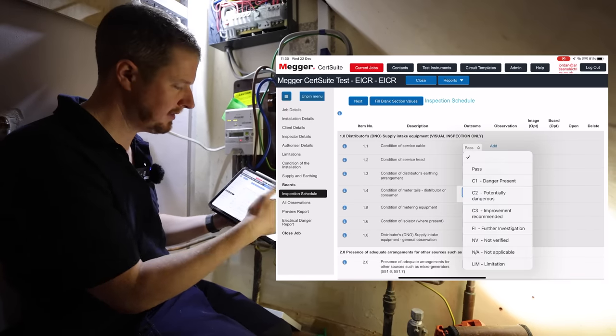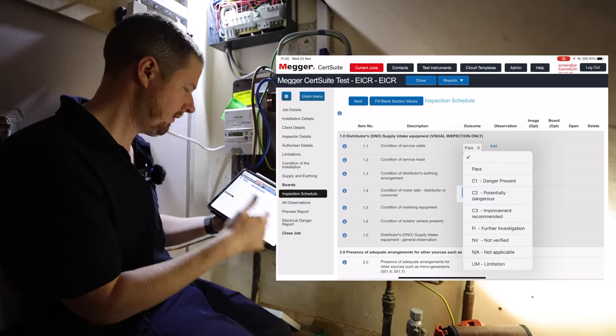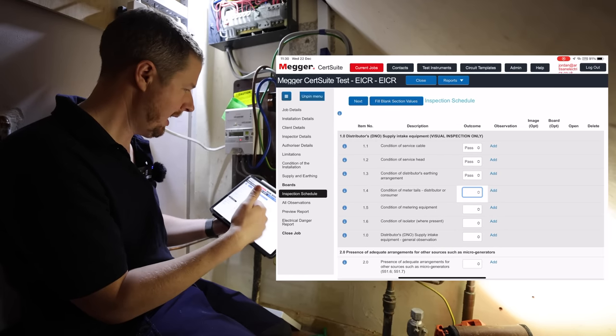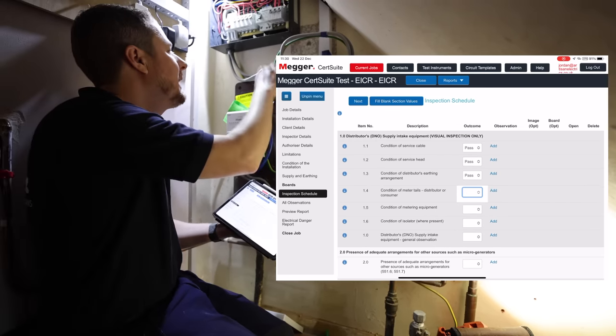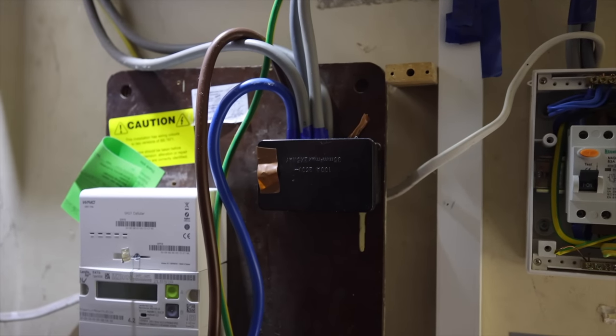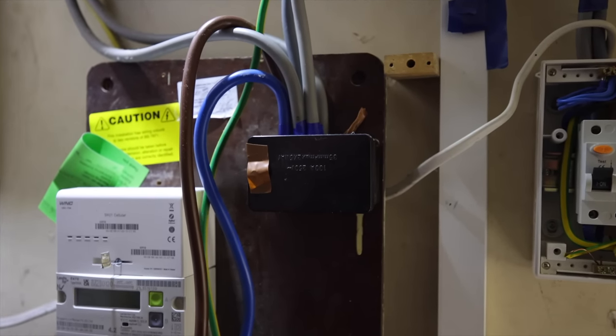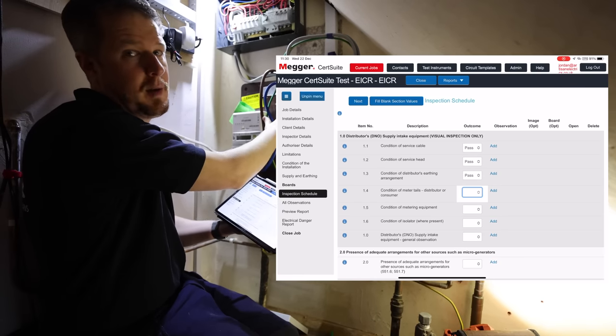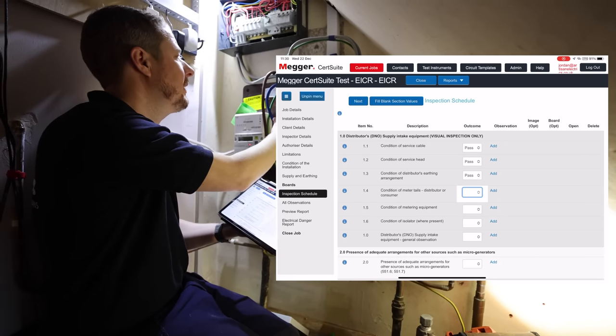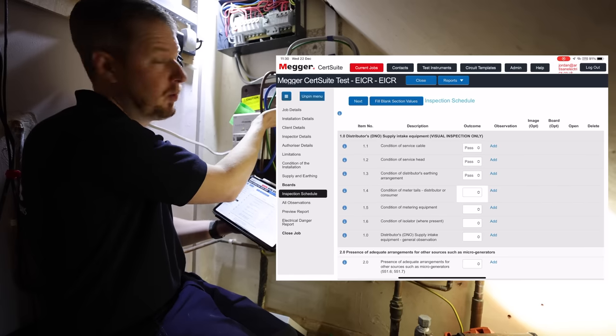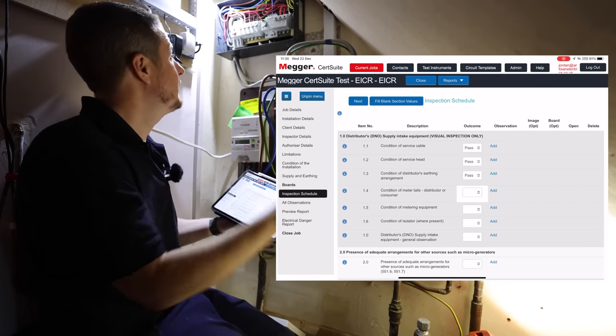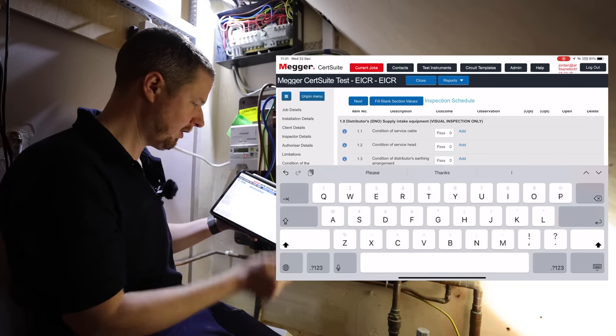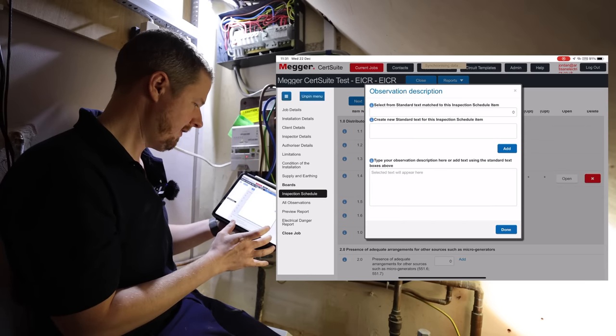So I'm just going to go through this. This is a bit boring, I'm not going to show you all of this, but it's just a tick box exercise going through. And if we find any issues, like the Henley block, for example, that is a codeable offense having it upside down, because the top surface does not comply with IPXXB or IP4X. It should be the other way around so the top surface is smooth with no holes, but they've just put it upside down. So we'll code that as a C2.